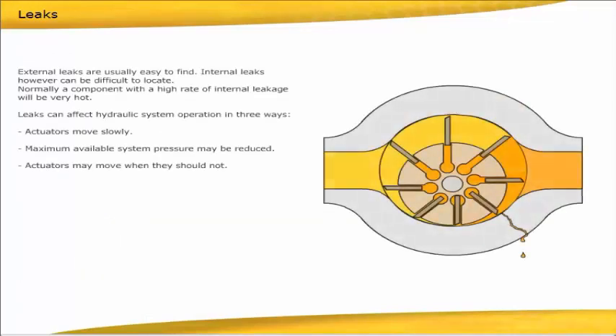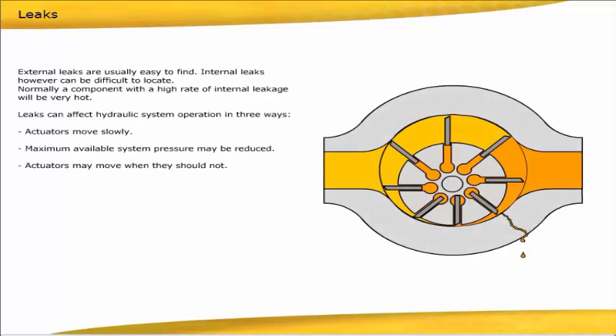External leaks are usually easy to find. Internal leaks, however, can be difficult to locate. Normally, a component with a high rate of internal leakage will be very hot. Leaks can affect hydraulic system operation in three ways: actuators move slowly, maximum available system pressure may be reduced, actuators may move when they should not.